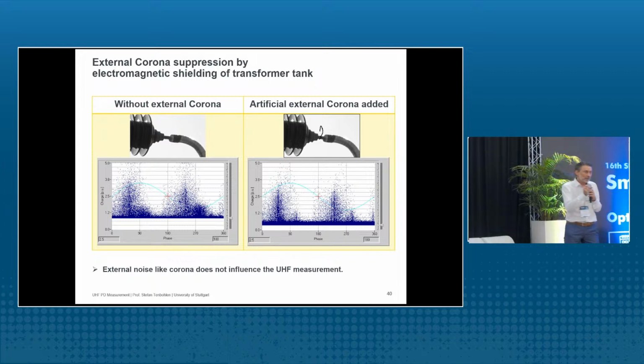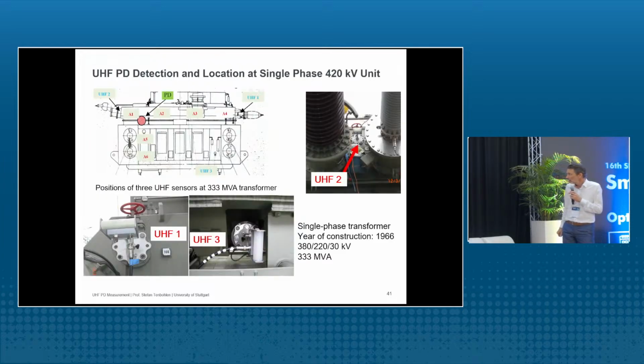The reason is, of course, that the bushing here has a capacitance to Earth, and the high frequencies which are generated by this external corona have, due to this capacitance, a short circuit path to the ground and do not come into the transformer tank.